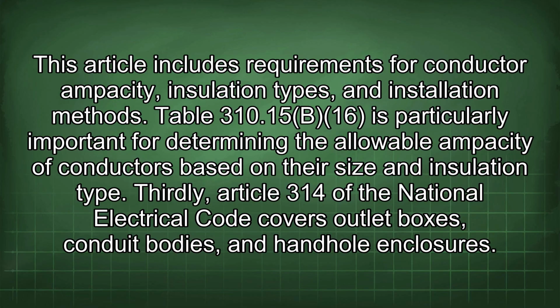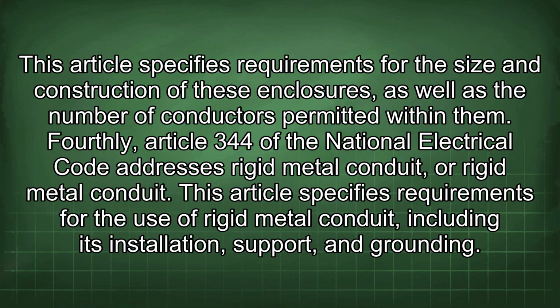Table 310.15(B)(16) is particularly important for determining the allowable ampacity of conductors based on their size and insulation type. Thirdly, Article 314 of the National Electrical Code covers outlet boxes, conduit bodies, and handhole enclosures. This article specifies requirements for the size and construction of these enclosures, as well as the number of conductors permitted within them. Fourthly, Article 344 of the National Electrical Code addresses rigid metal conduit. This article specifies requirements for the use of rigid metal conduit, including its installation, support, and grounding.